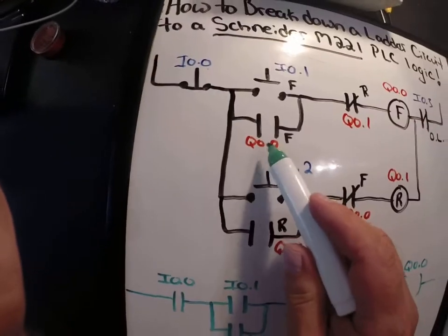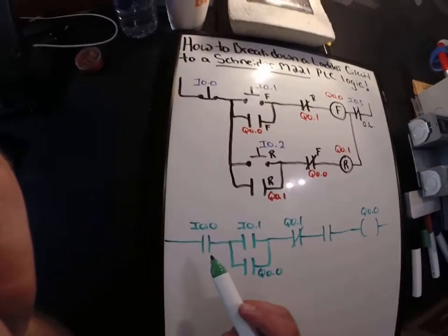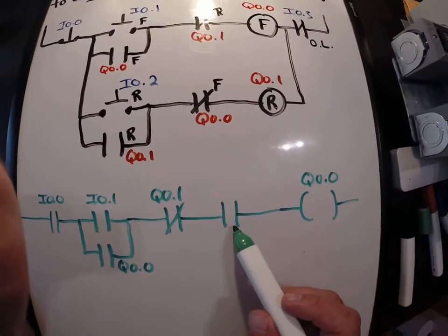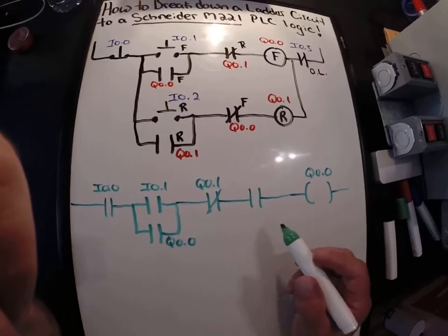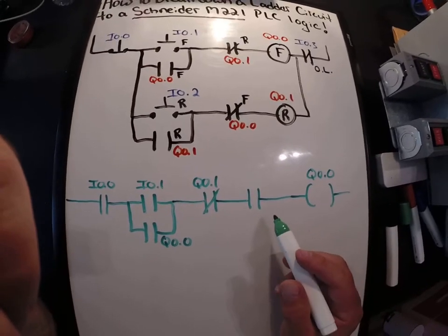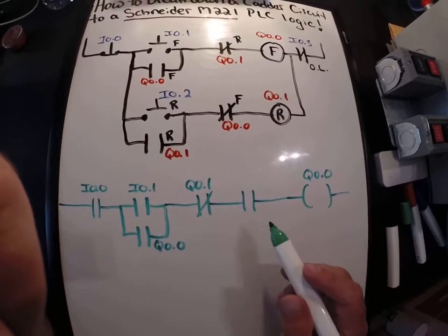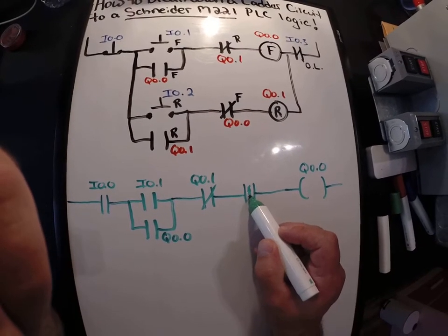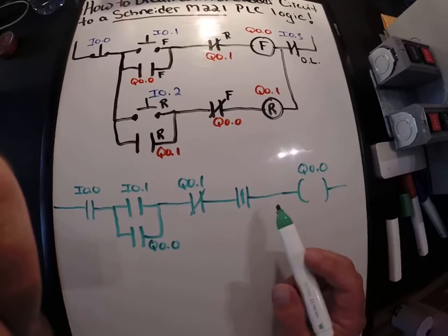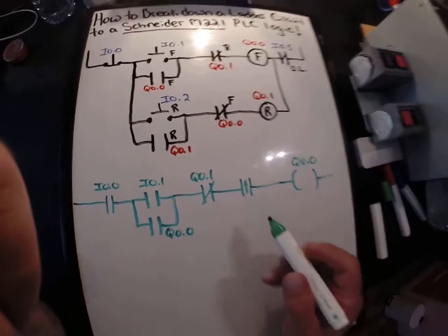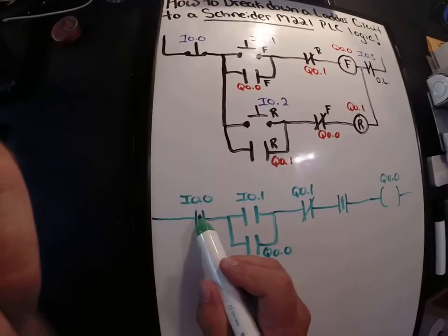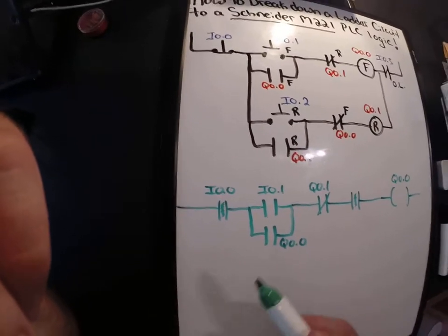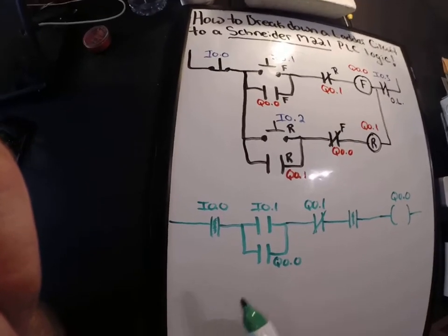Once again, that's that. Now I made my stop normally open, and I made my overload normally open, because in our lab we want to simulate them with a single pole switch. Now pretend that the switch is in the on position, the circuit would be closed. So the PLC, when you have your stuff all wired in, this will actually be shaded in green. Same thing with a stop button. That's going to be shaded in green, which means it's true and there's a path for current flow.